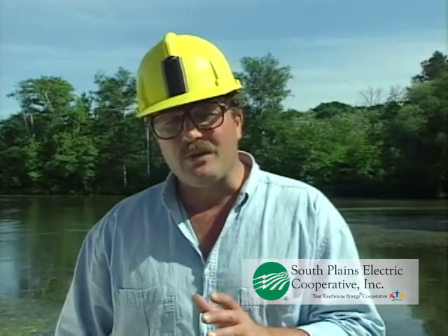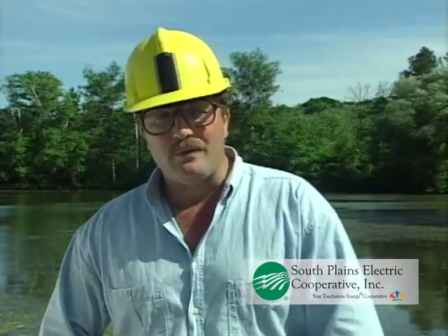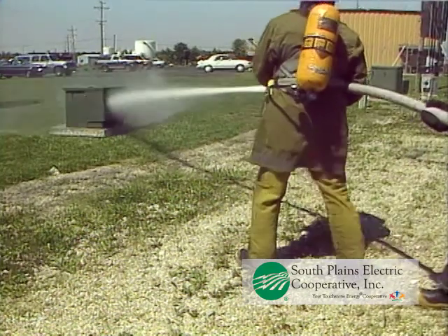Understanding the concept of potential difference is critical to your safety. Electricity will take any and all conductive paths to return to its source. Objects that allow the passage of electrical current are known as conductors. We're surrounded by conductive objects, many of which do not appear at all like wires. For example, water — water is an excellent conductor of electricity. Attempting to extinguish a fire involving energized electrical equipment with a water stream is like attacking with a bare wire. It could be a fatal mistake. The human body is mostly water and is therefore an excellent conductor. Other familiar objects, such as tree branches, pike poles, and ladders, are potential conductors as well.